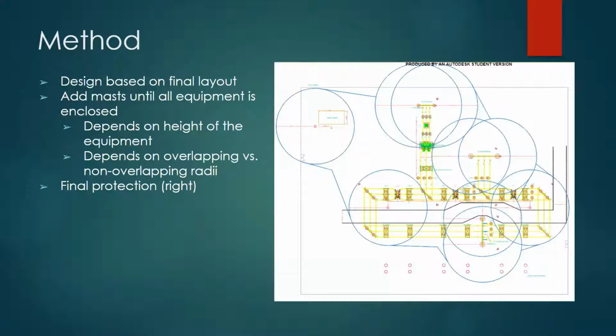So to start out our design, we had to finish our layout for the substation first, and then we could kind of build off that. So our initial design of the substation had 6 lightning masts, and that's going to be 2 on each of the exits, as you can see here, here, and here. So then we just added masts until all the equipment was enclosed. So the protection that the mast would offer depended on the height of the equipment, and it also depended on whether the circle of protection that the mast offered was overlapping versus non-overlapping with another mast's circle of protection.